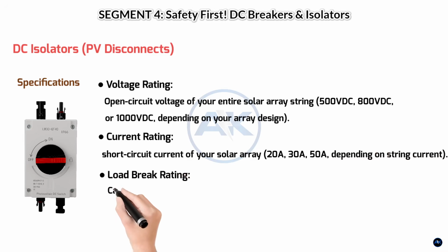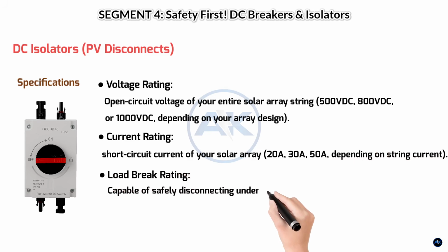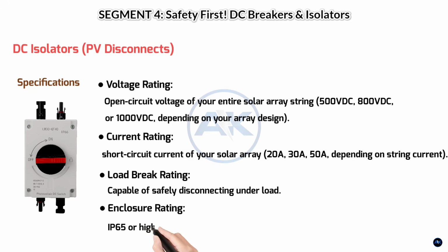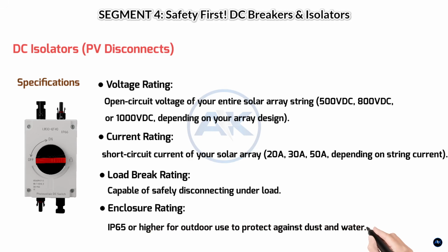Load break rating: capable of safely disconnecting under load. Enclosure rating: IP65 or higher for outdoor use to protect against dust and water. Why are they important? They provide a crucial safety point for maintenance, troubleshooting, and in case of emergencies, allowing you to completely de-energize the DC side of your system.